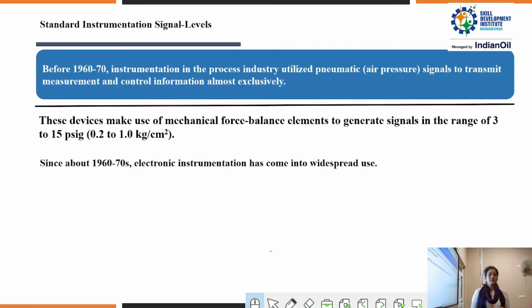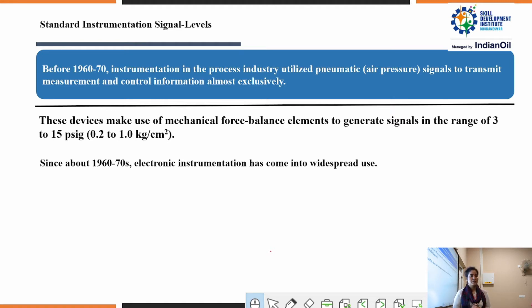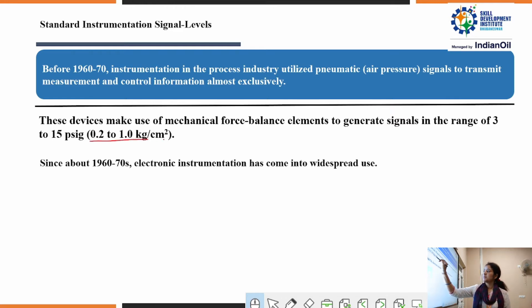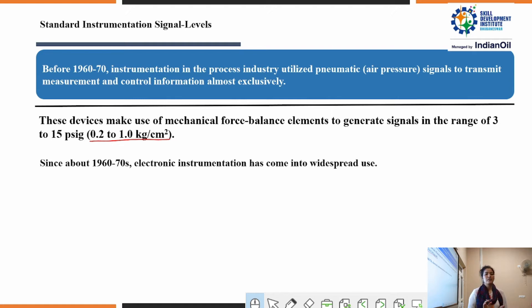In earlier times — the 1960s and 70s — instrumentation in the process industry utilized pneumatic pressure signals, that is air pressure, to transmit measurement and control information almost exclusively. Devices made use of mechanical force balance elements to generate signals in the range of 3 to 15 PSIG, which can be calculated as 0.2 to 1.0 kg per centimeter square. Since about the 1960s and 70s, electronic instrumentation has come into widespread use with various types of signals — voltage or current signals.